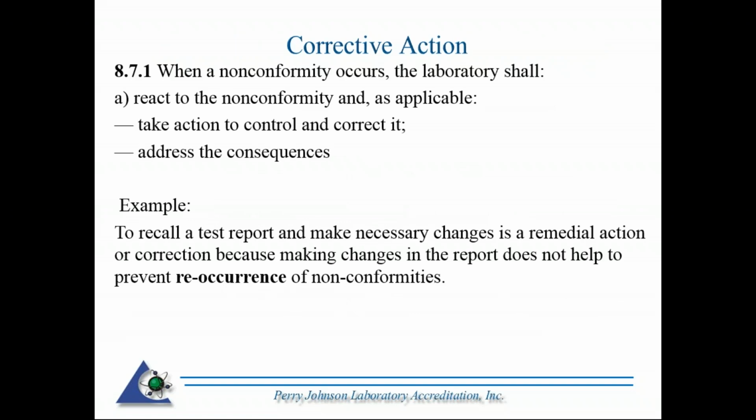Okay, so 8.7.1 kicks off with: when a nonconformance occurs, the laboratory shall, of course, react to the nonconformance and, as applicable, take action to control and correct it and address the consequences. So right there, we're looking at what I was referring to as correction. We're going to take action and control. We're going to contain the immediate situation at hand.